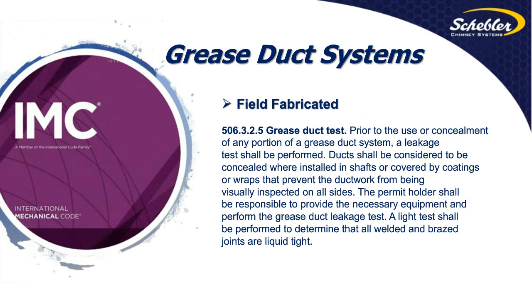Now, field fabricated systems would have to go through a grease duct test prior to any kind of covering of coatings or wraps that would be done. So that testing would be done as a light test to determine that all weld and braze joints are liquid tight. In essence, they would take a 100-watt light bulb inside the ductwork and visually make sure that no light would be visible on the outside of the ductwork and into weld seams of the system.